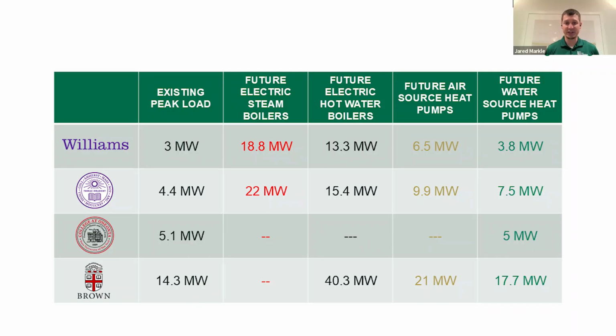We're working through with National Grid now what that looks like, and in a lot of cases it looks like a new upstream substation that might take 7 or 10 years to build. You have to plan out how your program extends from one spot to the other. We just talked about that with Dartmouth this morning. As we transition from steam to hot water at Dartmouth, what does that mean for a temporary electrical service? What does it mean for permanent electrical service? How do you factor in the fact that we're putting in 13 megawatts of diesel generators that have a 2.5-year lead time? And then how do they all play together?